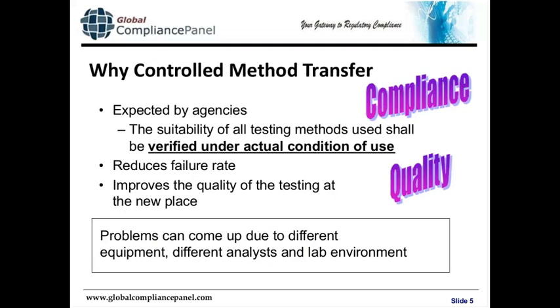This slide presents reasons why we should pay attention to controlled method transfer. When we talk about compliance, there are generally two reasons. Number one is to comply with regulations and meet the expectations of inspectors when they come into your laboratory for FDA or GMP compliance inspections. Equally important is to reduce failure rates and improve the quality of analytical results through a controlled method transfer process.